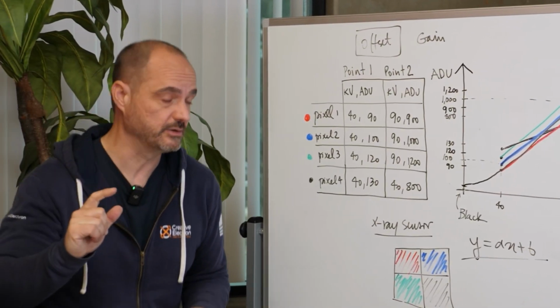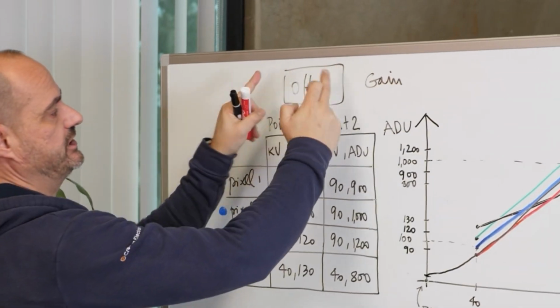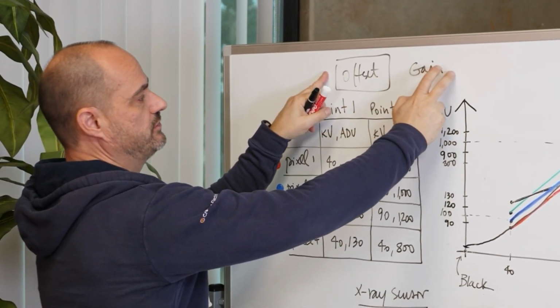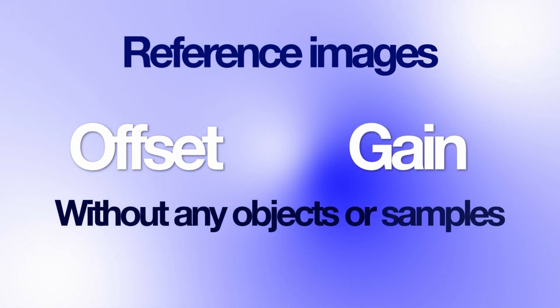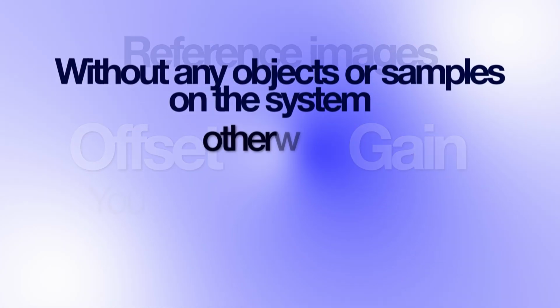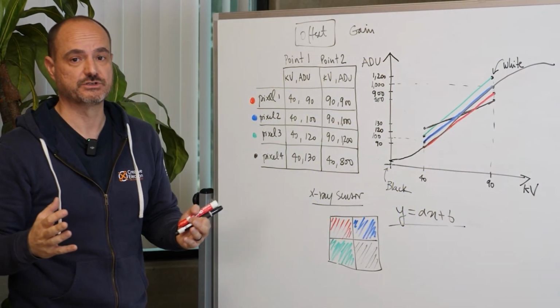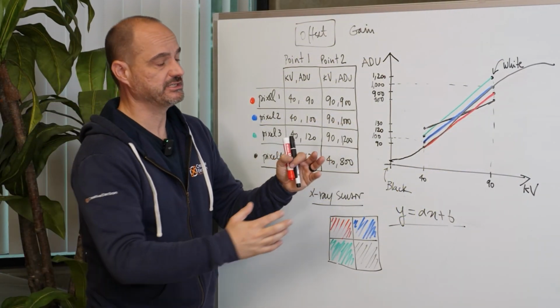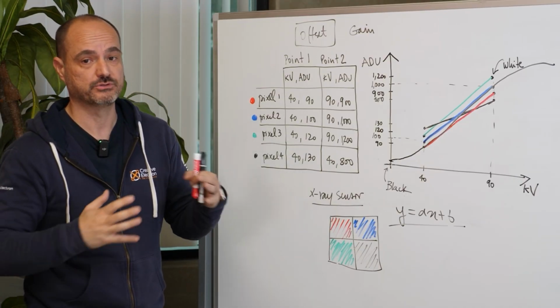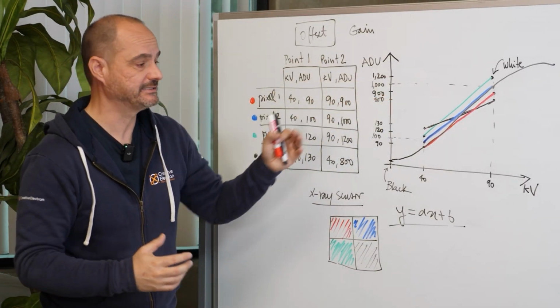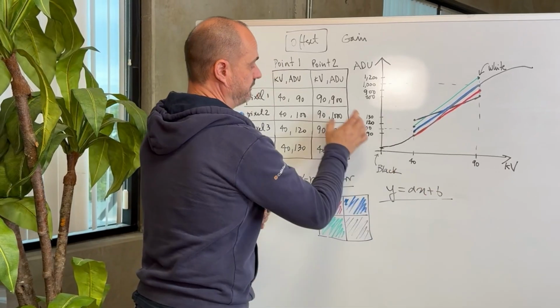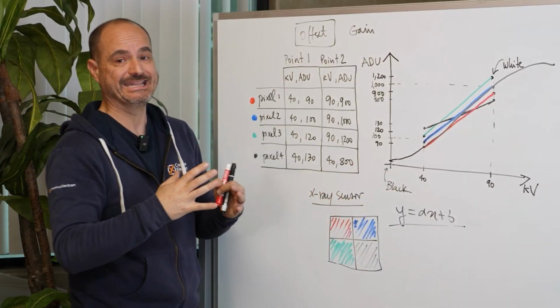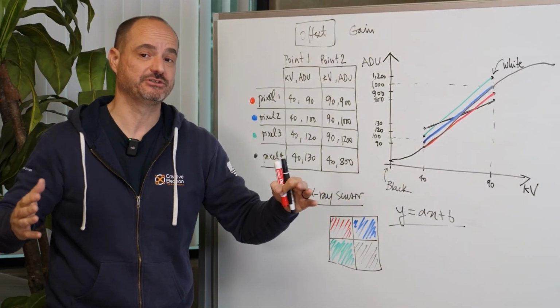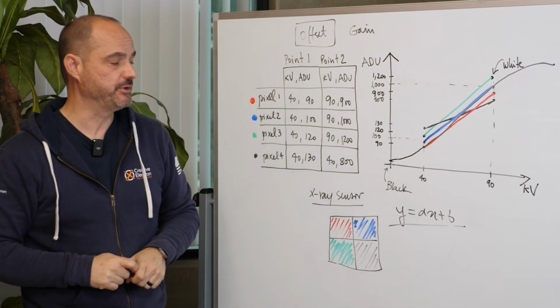Now, it's really important when you do the gain calibration and the offset image collection, those 2 reference images, that you do it without any objects or samples on the system, of course. Otherwise, you end up calibrating this sample into the image. We've had customers do that in the past, and we just help them with the process. You have to calibrate without any samples on the stage, because if you do that, the A and B values for the equation show up in that specific sample, and in every other image you take, you see the shadow of the sample you calibrated with.